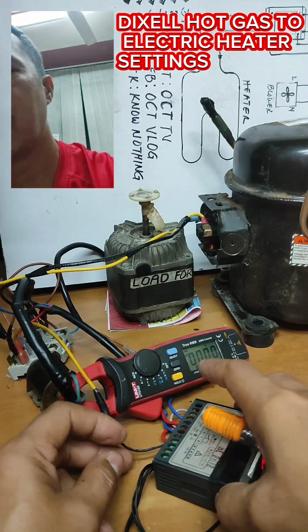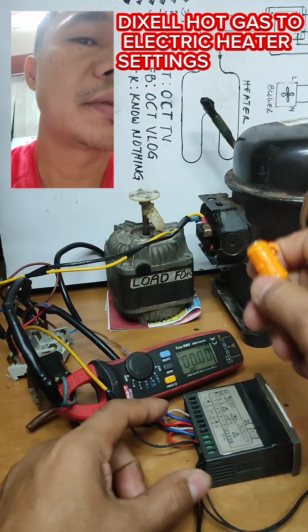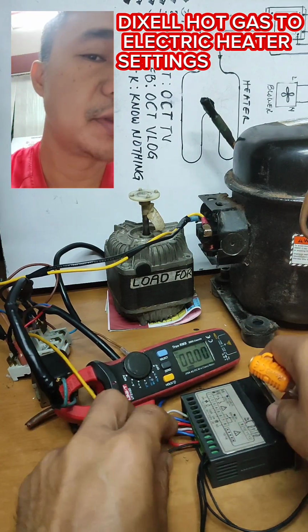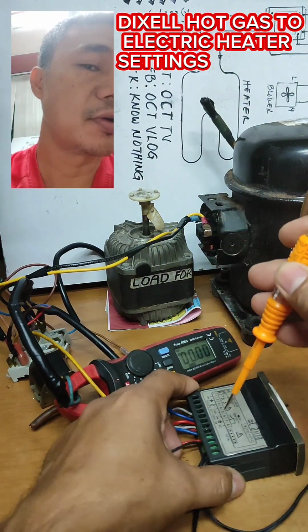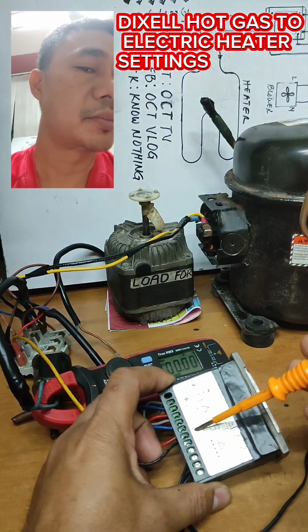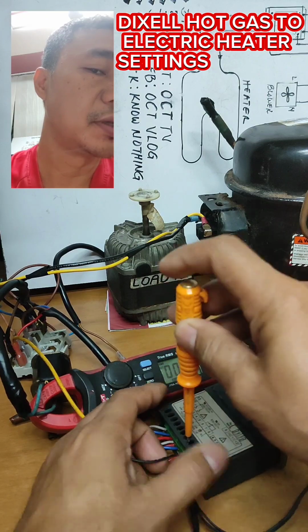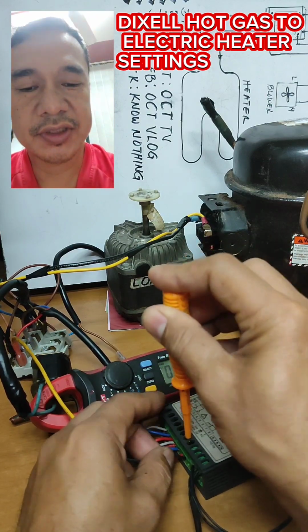And all you have to do, because the solenoid is shorted, is just uninstall terminal number 7, which is for the defrost.